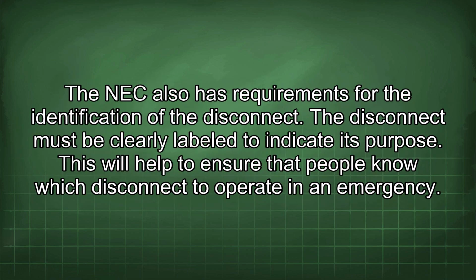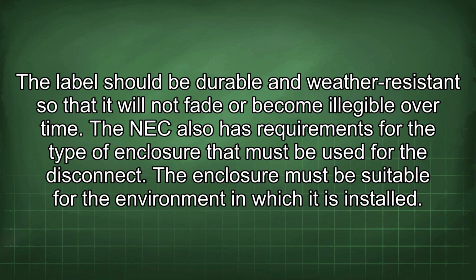The NEC also has requirements for the identification of the disconnect. The disconnect must be clearly labeled to indicate its purpose. This will help to ensure that people know which disconnect to operate in an emergency. The label should be durable and weather resistant so that it will not fade or become illegible over time.